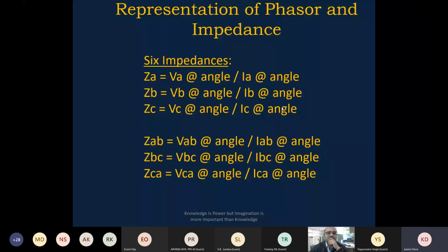According to the fault, the setting has to be implemented. So, for example, say the backup impedance relay normally calculates phase to phase fault or three phase fault, not phase to ground fault. The phase to ground fault loop is off, as is normal in a thermal power station. The reason is the generator is grounded and the GT is a delta star.